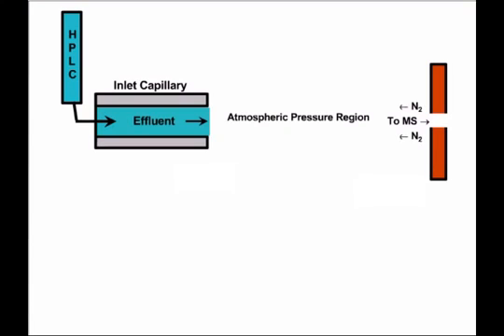Flowing counter to the direction that the ions travel is a counterflow of a heated drying gas, and this is typically nitrogen. With this nitrogen drying gas, along with a nitrogen nebulizing gas — which may or may not be present depending upon the design of the electrospray interface — and the atmospheric gases already present in the atmospheric pressure region, this is largely nitrogen. Most of the oxygen and other gases have been displaced by the use of nitrogen.